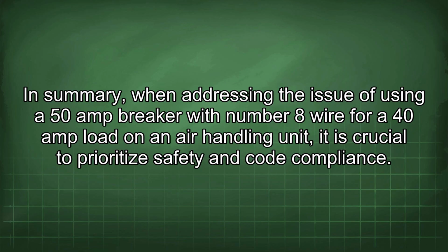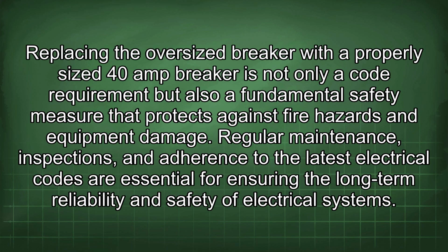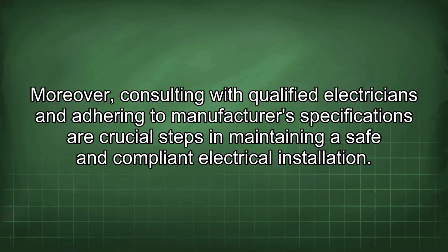In summary, when addressing the issue of using a 50 amp breaker with number 8 wire for a 40 amp load on an air handling unit, it is crucial to prioritize safety and code compliance. Replacing the oversized breaker with a properly sized 40 amp breaker is not only a code requirement, but also a fundamental safety measure that protects against fire hazards and equipment damage. Regular maintenance, inspections, and adherence to the latest electrical codes are essential for ensuring the long-term reliability and safety of electrical systems. Moreover, consulting with qualified electricians and adhering to manufacturer's specifications are crucial steps in maintaining a safe and compliant electrical installation.